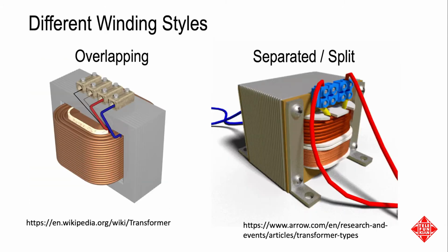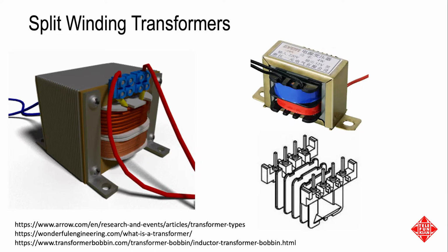There are different approaches to winding transformers, even those on common EI cores. They can be wound in an overlapping fashion, where the primary and secondary windings are wound on top of one another, sometimes overlapping in alternating layers, or the primary and secondary windings can be wound separately in a split winding. This latter approach has considerable safety benefits, as the consequences of a winding failing are generally less severe because the primary and secondary windings never come into physical contact.